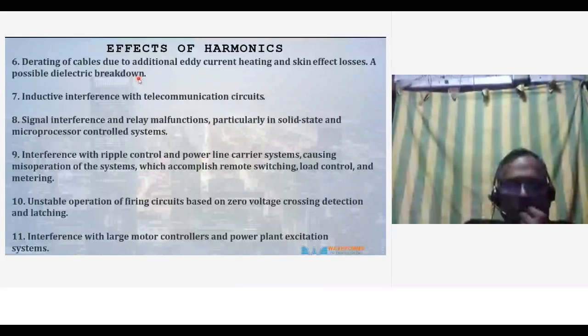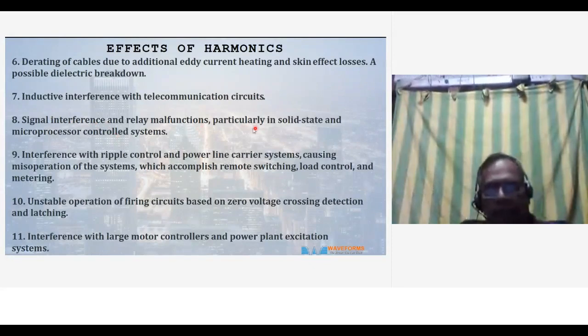Derating occurs due to additional eddy current heating, skin effect, and possible dielectric breakdown. So this happens in the cables. Inductive interference with telecommunication systems happens sometimes when telecommunication cables run close to the electrical cables. And signal interference and relay malfunction, particularly in solid state and microprocessor control systems. Interference with ripple control and power line carrier systems, causing maloperation of remote switching, load control and metering. So anything digital is a serious problem.